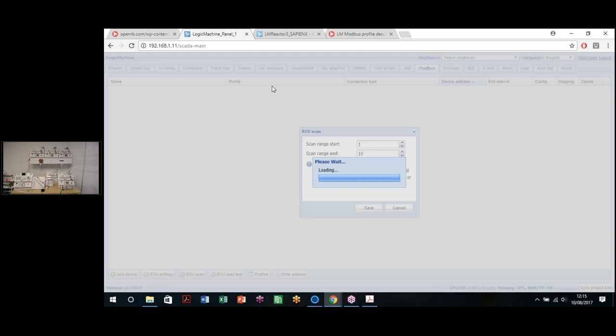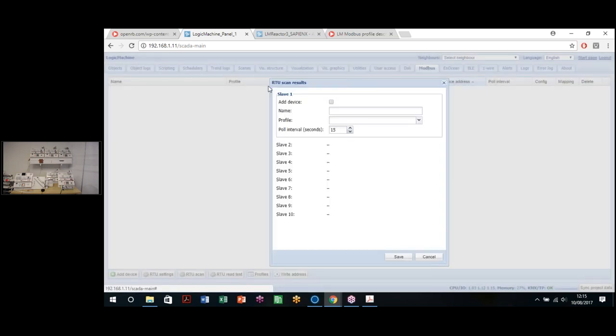This can take up to 30 seconds, as we read before. When that finishes, we have, of course, two ways of adding a Modbus device. We can add it using this tool, which is the RTU scan. When we click Add Device, in this case, I'm going to name this thermostat 2, because we created one thermostat previously, and we select the profile that we have created, and a poll interval to detect the information of the Modbus. In this case, I'm going to leave it this way and save.